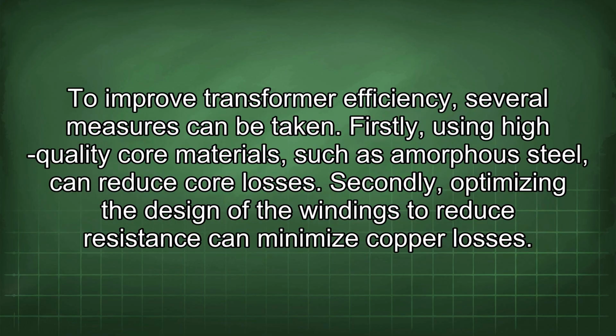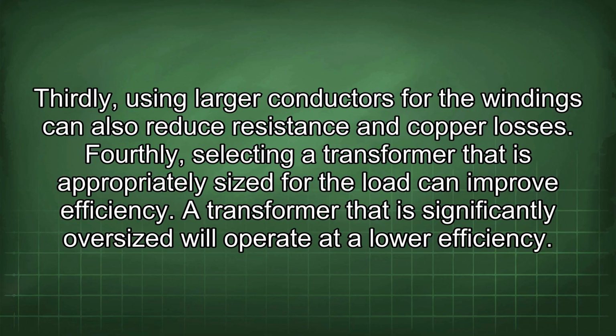To improve transformer efficiency, several measures can be taken. Firstly, using high-quality core materials, such as amorphous steel, can reduce core losses. Secondly, optimizing the design of the windings to reduce resistance can minimize copper losses. Thirdly, using larger conductors for the windings can also reduce resistance and copper losses. Fourthly, selecting a transformer that is appropriately sized for the load can improve efficiency.